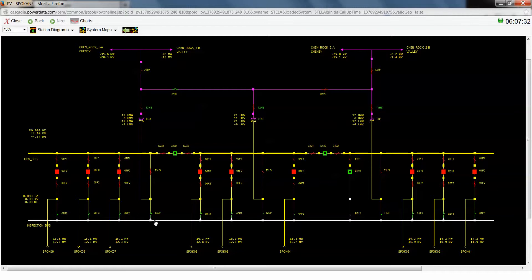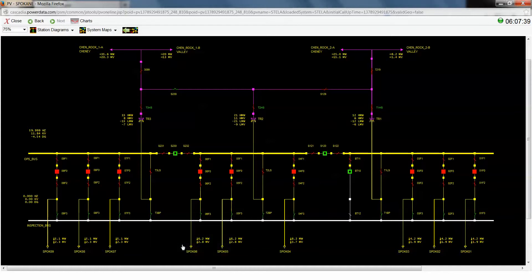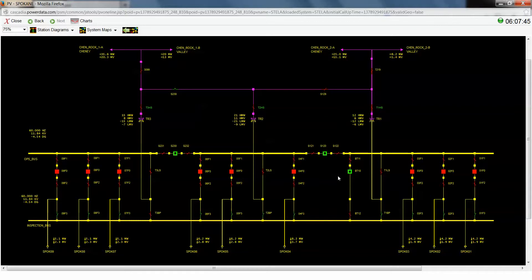And we're actually going to energize this inspection bus through our bypass switch. Now the reason that we do this is because when we actually put these transformers in parallel, we're going to be making that parallel across this bus tie because you always want to make a parallel, make or break a parallel using a circuit breaker. So now you can see our inspection bus is energized, we're up to our proper voltage.